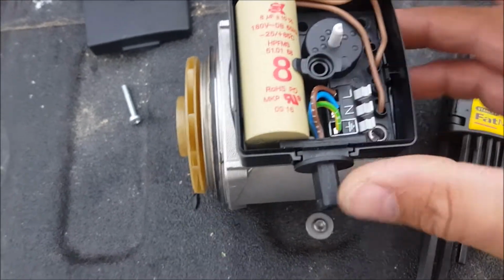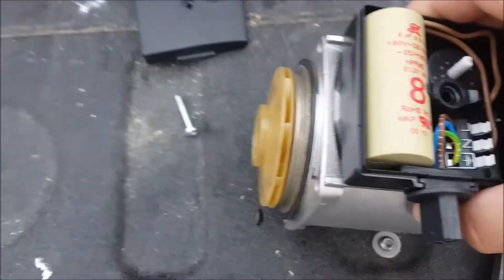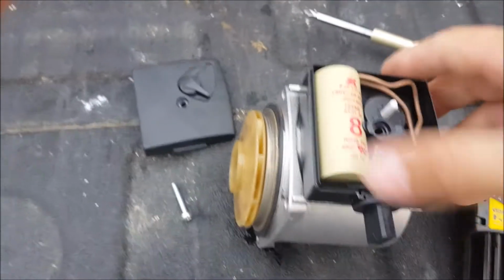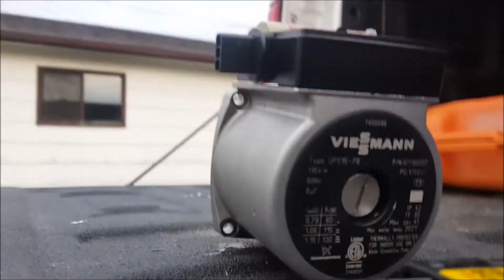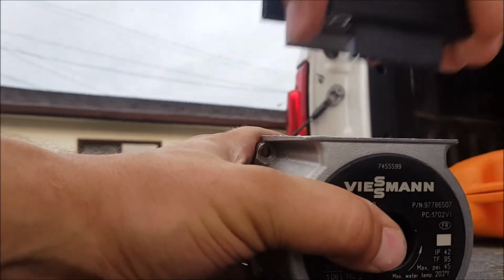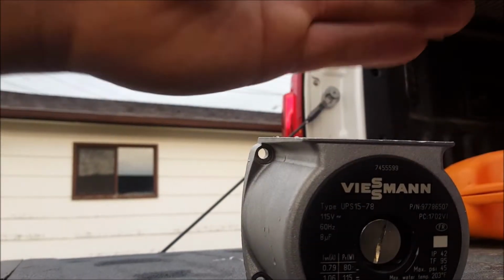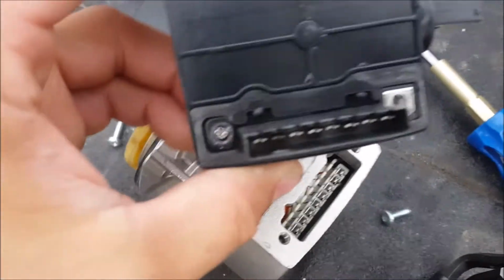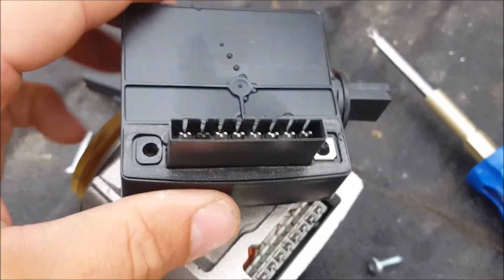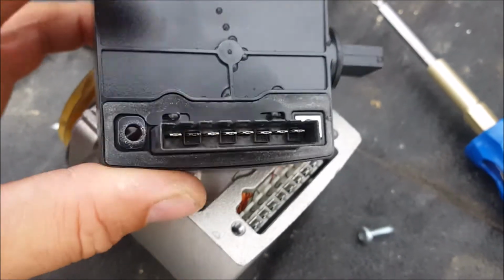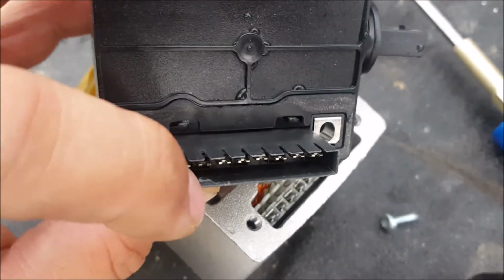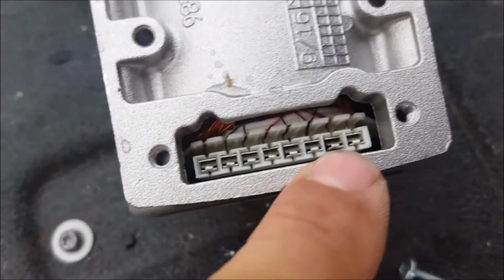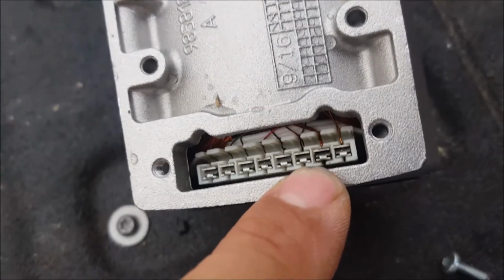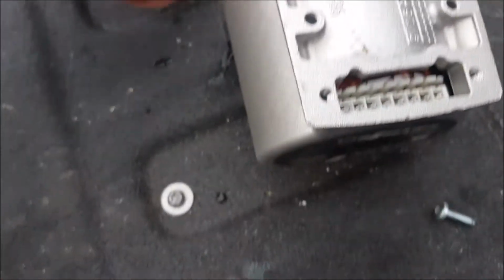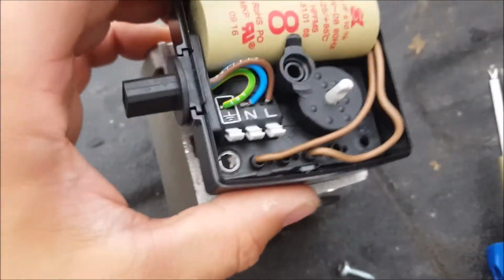These pins also have to be in here. But where the problem was with this one - this all checked out - was underneath here, where this plugs in. If you look down in here, see that one pin is black. It might be hard to see, but that one pin is black, and you can see down here, there's arcing. So it had a pin fitment issue on that pin, which you can see is also darker. That pin was lazy and wasn't clamping down. We call that a pin fitment issue. So this wasn't making good purchase.